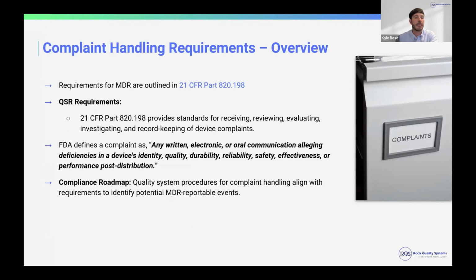The FDA defines a complaint as any written, electronic, or oral communication alleging deficiencies in a device's or diagnostic's identity, quality, durability, reliability, safety, effectiveness, or performance. So complaints are a critical part of medical device quality systems and ongoing compliance. It's really essential that you process any feedback you get regarding your LDT device and then determine whether or not that is a complaint.